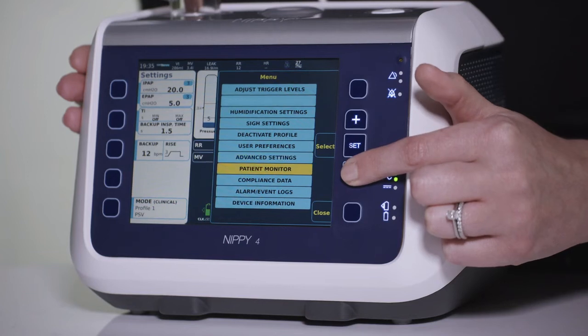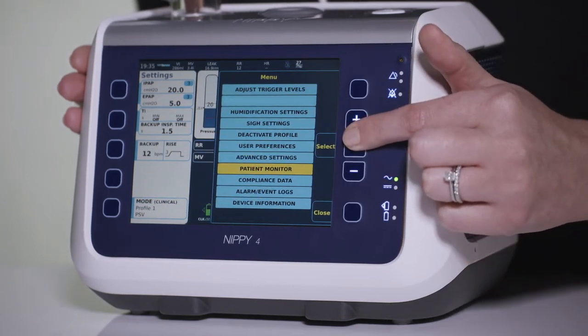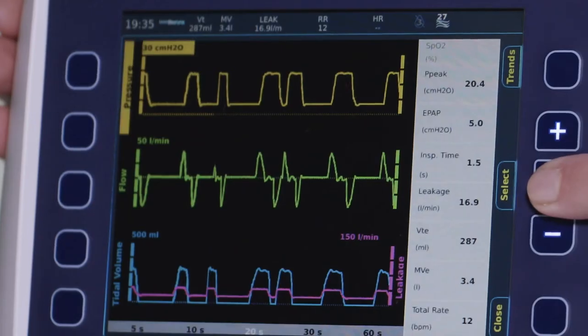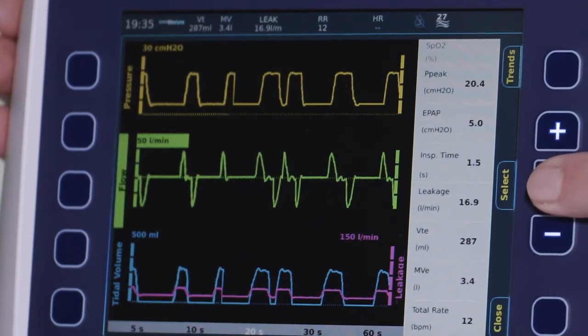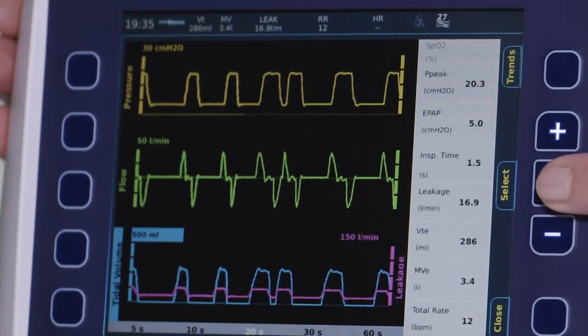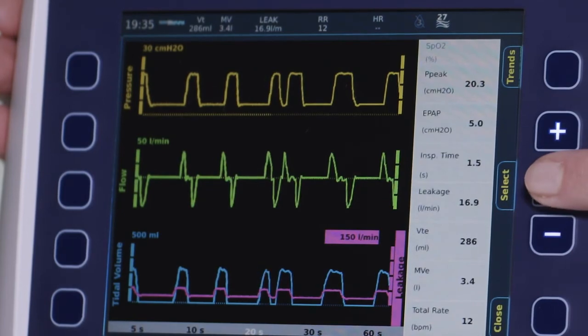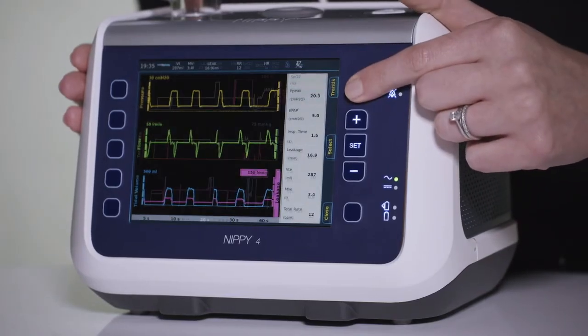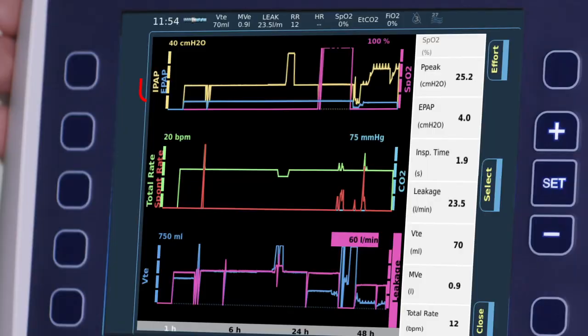When you enter the Patient Monitor section of the main menu during treatment, you can view the patient's pressure, flow, tidal volume and circuit leakage waveforms. By pressing the top right Trends button, you can then view the patient's trend data for IPAP, EPAP pressures, total breath rate versus their spontaneous breath rate and their SpO2, tidal volume and circuit leakage.